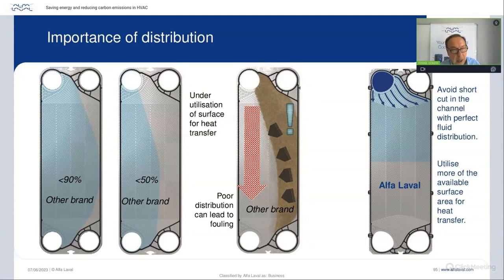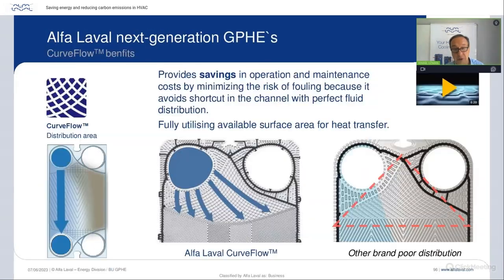start of fouling. And let's say, at part load with a cooling tower application, half load means quarter the velocities, and then the fouling, which begins at this dead spot, moves to the left, until the water in this channel is just going from port to port, and this is not what we want. So that's the importance of the Alfa Laval curve flow, which is developed only in the last 2-3 years, and is available with all our products, all our model sizes of heat exchangers, which is very, very good.